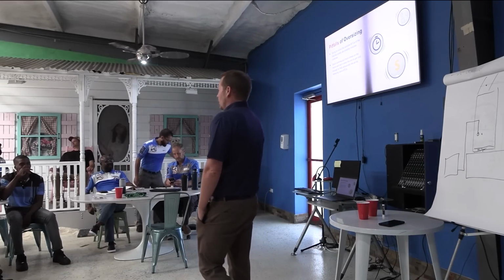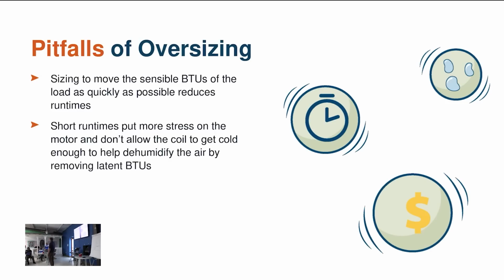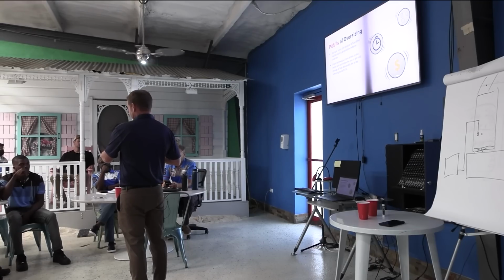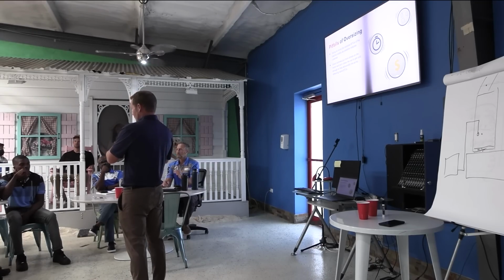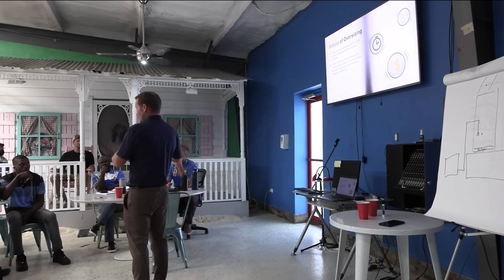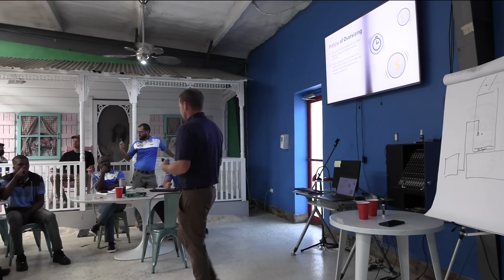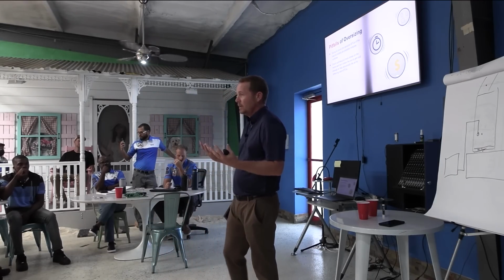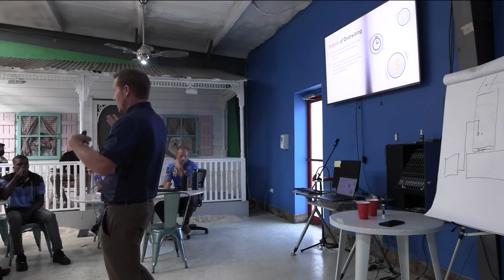Another thing I want to mention quickly is oversizing and short cycling - that's a really big problem a lot of people don't think about. When a system short cycles, it never really has a chance to get cold enough on the coil. So long run time is really important, because if the system shuts off, it's going to take it 5+ minutes again for that coil to get to dew point and start building up moisture again. Systems that short cycle are a really big problem - you may have a system that gets a cold coil, but if it's cycling on and off, that's an issue.